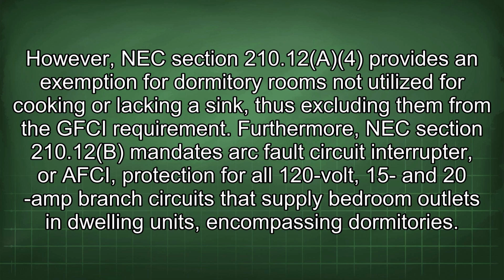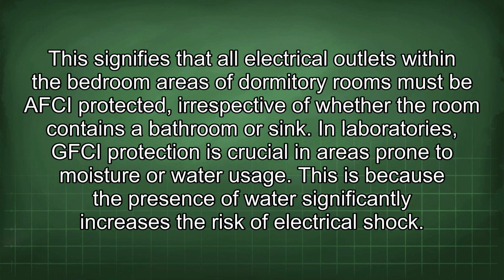Furthermore, NEC Section 210.12(B) mandates arc fault circuit interrupter, or AFCI, protection for all 120 volt, 15 and 20 amp branch circuits that supply bedroom outlets in dwelling units encompassing dormitories. This signifies that all electrical outlets within the bedroom areas of dormitory rooms must be AFCI protected, irrespective of whether the room contains a bathroom or sink.